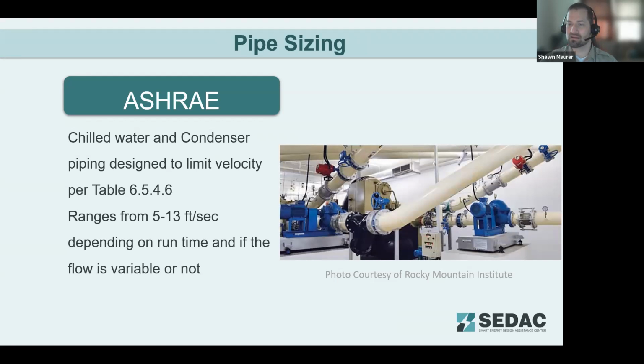Pipe sizing. Beyond standard pipe sizing practices, ASHRAE goes a bit further for sizing chilled water and condenser piping, limiting the velocity in the piping, as noted here, can limit the pressure drop per foot of pipe. It should be further noted that limiting bends and minimizing the length of pipe will further reduce pressure drop, which may enable smaller pumps to be used for these cooling systems. The photo that we've included here illustrates taking this to kind of a high degree. There's not a single 90-degree bend in this piping system. But the ASHRAE requirement here is specifically tuned towards looking at the velocity of flow in that pipe. Again, as velocity increases, the friction rate in the pipe increases and you increase your pumping requirements.